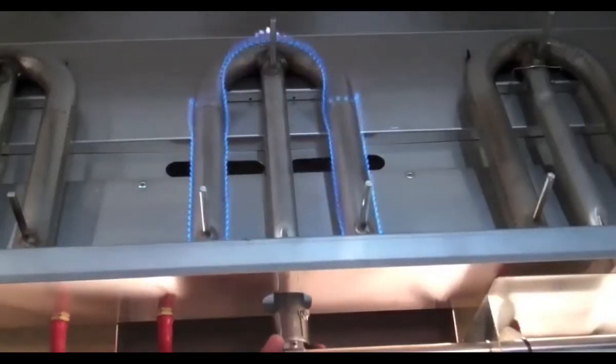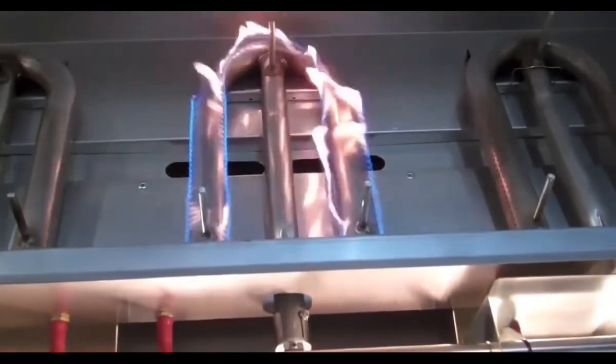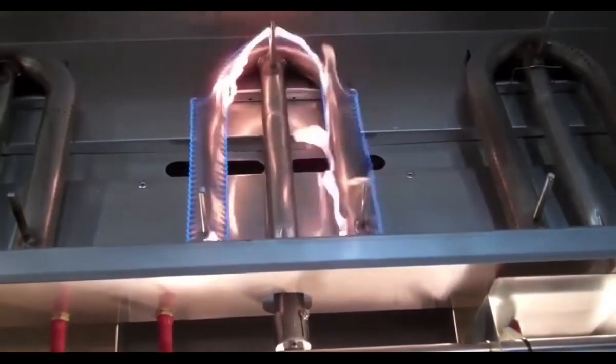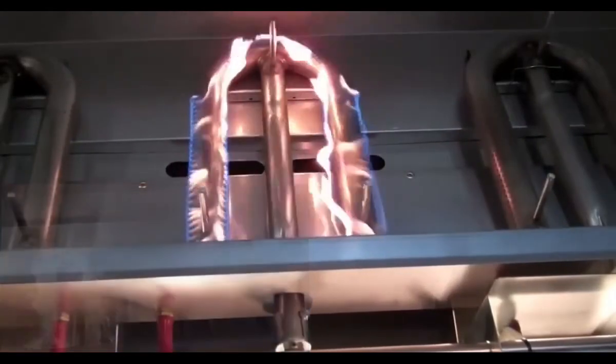Adjust the air shutter too far closed and gas flows into the burner pure without mixing with oxygen which causes flames to burn very yellow, very tall and will produce a lot of black carbon fumes.